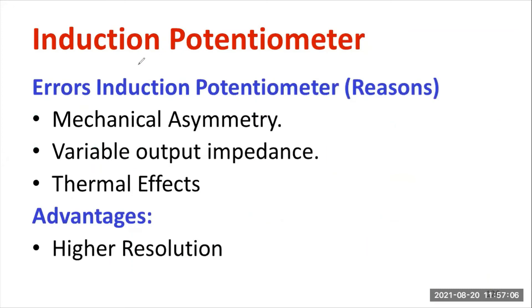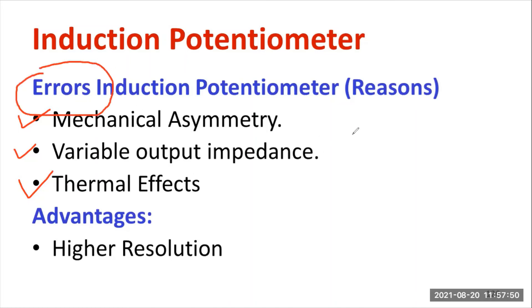Let us list out a few drawbacks of the induction potentiometer. There are certain errors which occur. The first is mechanical asymmetry — as the structure of the rotor connected to the shaft shows some mechanical asymmetry. Variable output impedance is also a reason for error, as impedance variation causes changes in the output voltage and affects accuracy. Thermal effect also matters a lot for the occurrence of errors in the induction potentiometer.